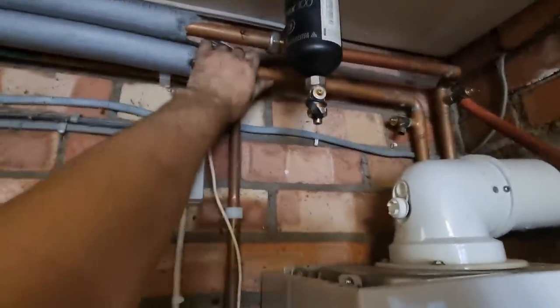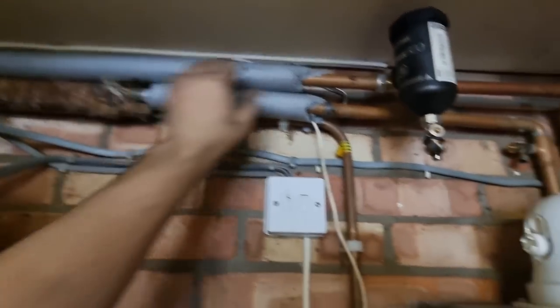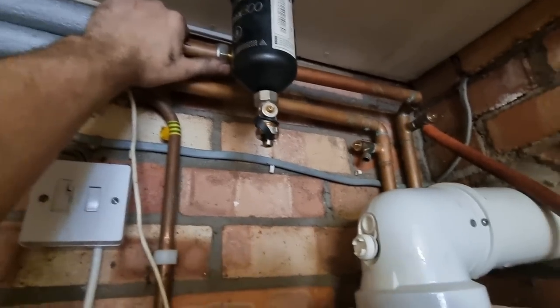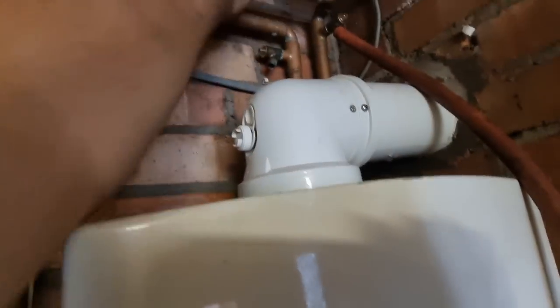I've just got the hot water on. If you're struggling with air, just put your hot water on, because I tend to find it's easier to pull it through. Flow's red hot now. Return is getting there. There's still too big a difference really, but the boiler's running away nicely. It's still firing just for hot water.